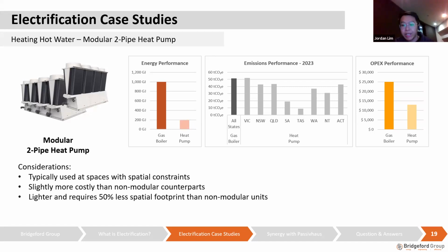For modular heat pumps, the performance is slightly lower, although quite similar to a commercial scale 2-pipe heat pump. As I mentioned earlier, it's suitable to be used in places like apartments or tall office buildings where there is limited plant space. The footprint is much smaller and a little bit lighter as well, up to 50% smaller, although it is slightly more expensive to implement because of the modularity and the better flexibility.